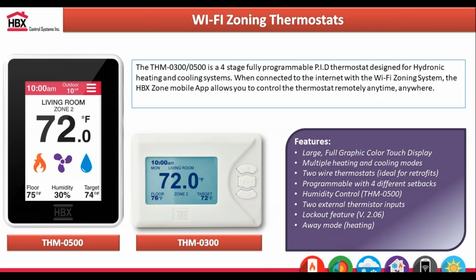With our stats for the Zone 550, again, you can use the 500 or the 300 series. In terms of functionality, there's no difference except for humidity control. If you need humidity control, then you need to go to our touchscreen stat, but for anything else, there's no difference in functionality. Again, you can have 2 stages of heating and 2 stages of cooling for each stat if you wanted to. You could have heat only, or 2 heat only with cooling, so you have about 8 or 9 different options in terms of your heating and cooling types.